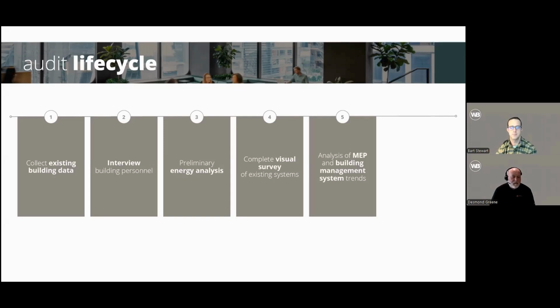We build a full energy audit by performing these calculations for each EEM, developing a big picture of how they'll positively impact energy usage in your building. Circling back to interviewing building personnel—if your building has clean rooms or similar spaces requiring certain air changes or air volume, you can't slow down the airflow. That's why it's critical to work with your team to understand how the building operates, so we don't recommend something that would negatively impact operations.